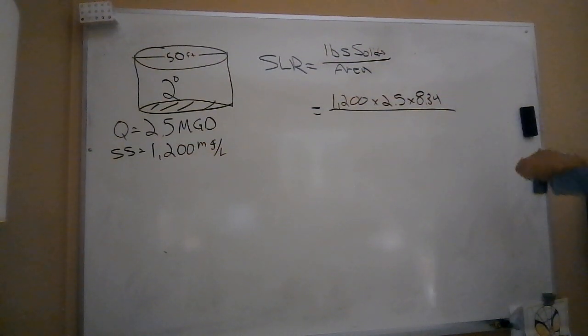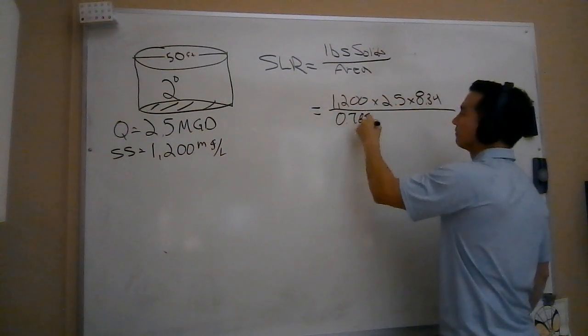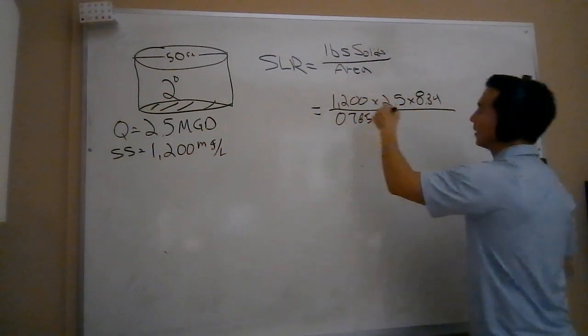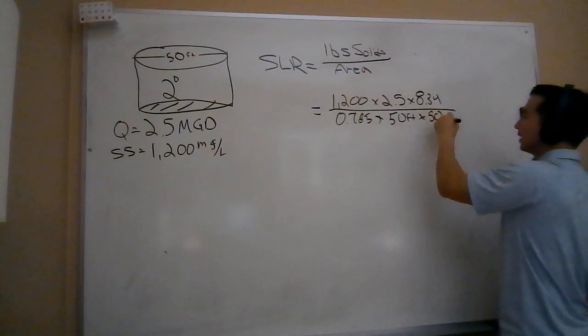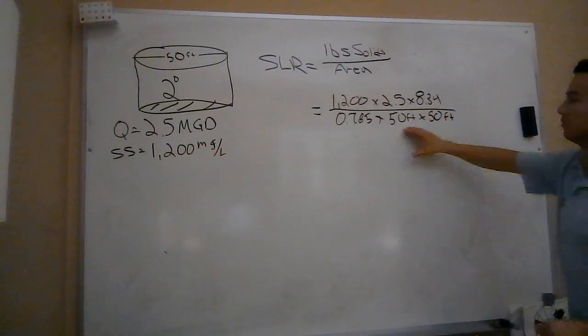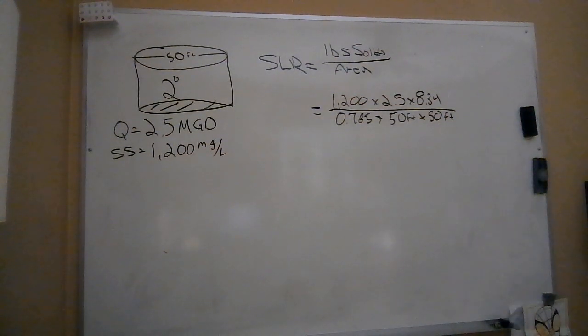Now I need to calculate the area of my clarifier. In water math, that's going to be 0.785 times my diameter squared - in this case, times my 50 feet times my 50 feet. This is the area available for solids to settle out. Let's run our handy dandy calculators here.